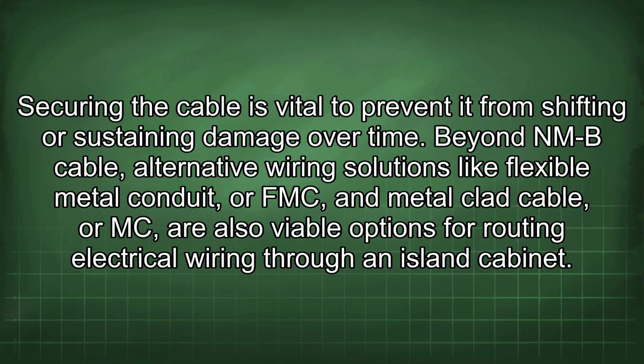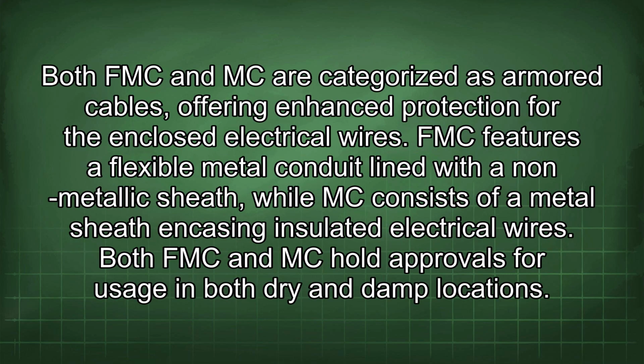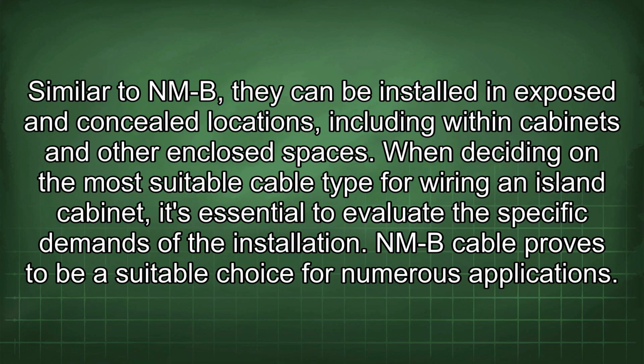Beyond NMB cable, alternative wiring solutions like flexible metal conduit, or FMC, and metal-clad cable, or MC, are also viable options for routing electrical wiring through an island cabinet. Both FMC and MC are categorized as armored cables, offering enhanced protection for the enclosed electrical wires. FMC features the flexible metal conduit lined with a non-metallic sheath, while MC consists of a metal sheath encasing insulated electrical wires. Both FMC and MC hold approvals for usage in both dry and damp locations. Similar to NMB, they can be installed in exposed and concealed locations, including within cabinets and other enclosed spaces.